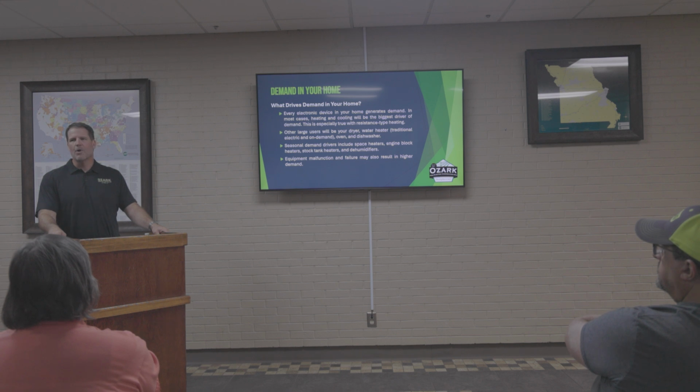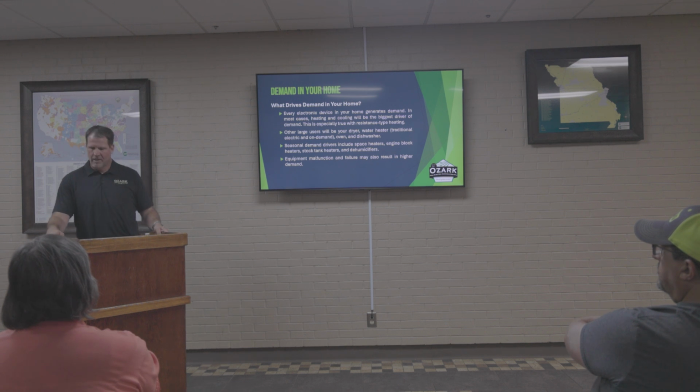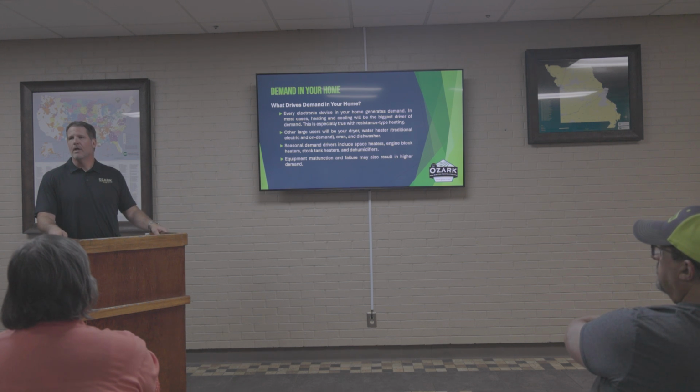We've seen a lot of times where those units are heating and cooling at the same time. We see that more than you would think. So there's a system that's malfunctioning, and that's going to create a higher demand. Sometimes we have a well that's been hit by lightning that's running continuously. Different things like that would be a malfunction that results in higher demand.